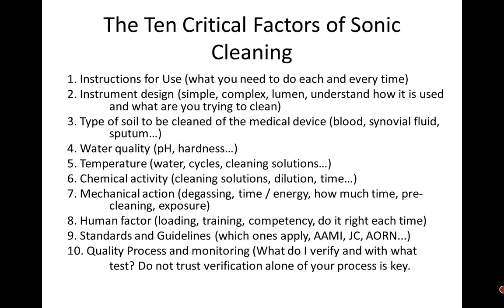So the mechanical action, how are you degassing? Do you have the right amount of time that you're exposing the instruments according to the IFU? This is all very, very important because you don't want to underexpose them. And as you saw on the slide earlier, it says minimum time. So you need to make sure that you meet that minimum requirement.